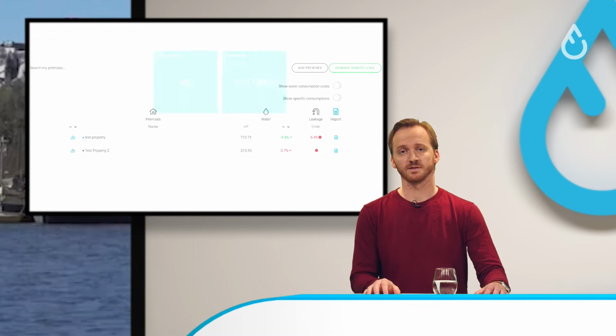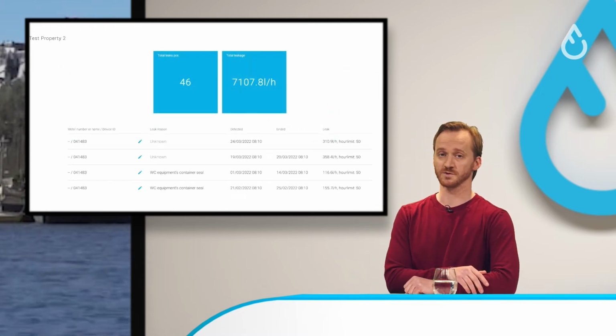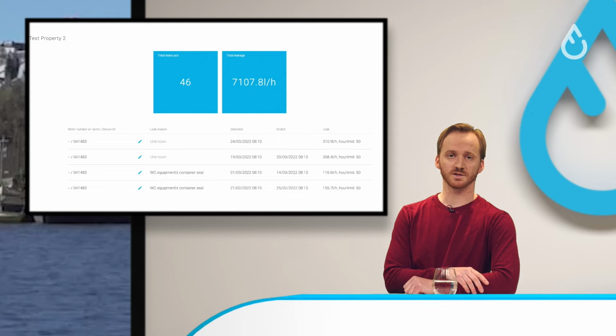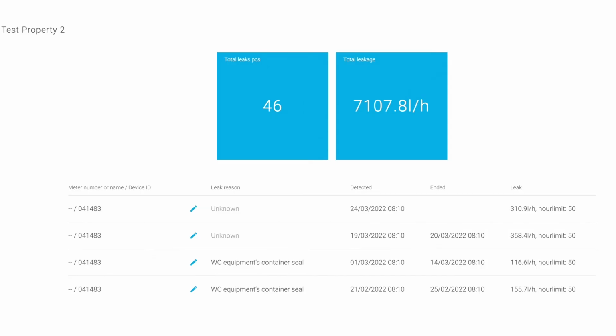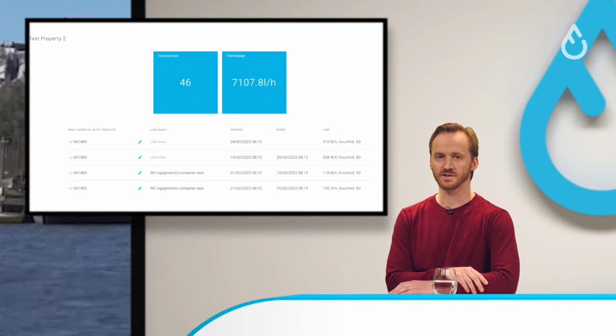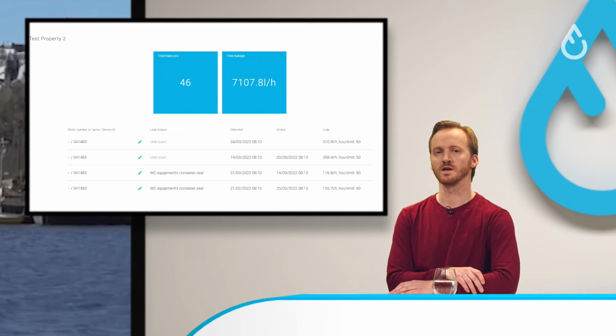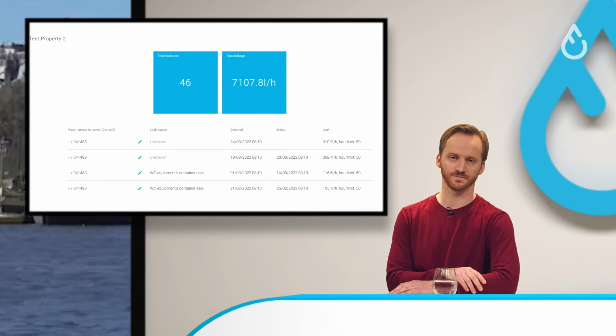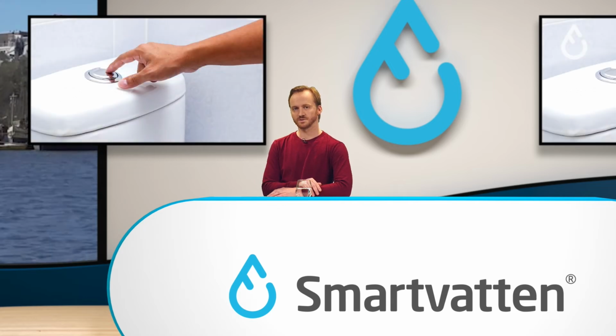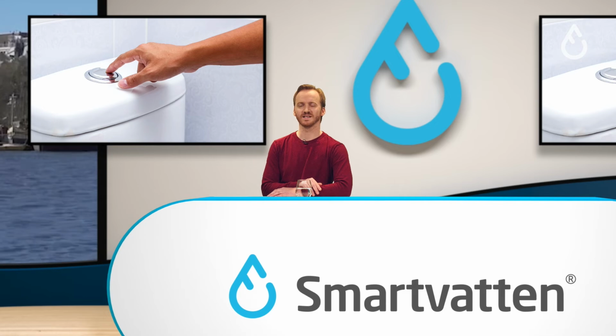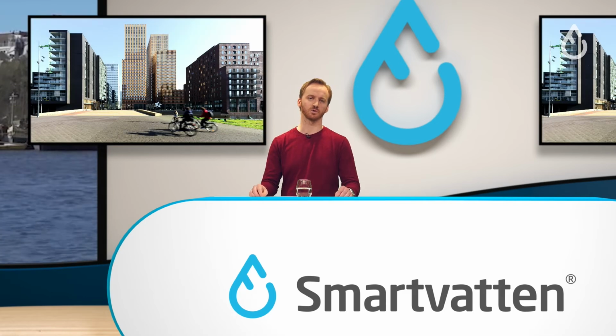So when we click this leak, it looks a little bit different from the minute level service. You see an overview of the leaks, and which volume of each leak was above the limit. Based on this information, with more than 300 liters used per hour during the night, we can safely say this is a leak. To most people, this sounds like a lot, but with these numbers, smaller water points are often the cause. That's why the hourly service level is fine for an office building, but not for a property where water is consumed 24 hours a day.